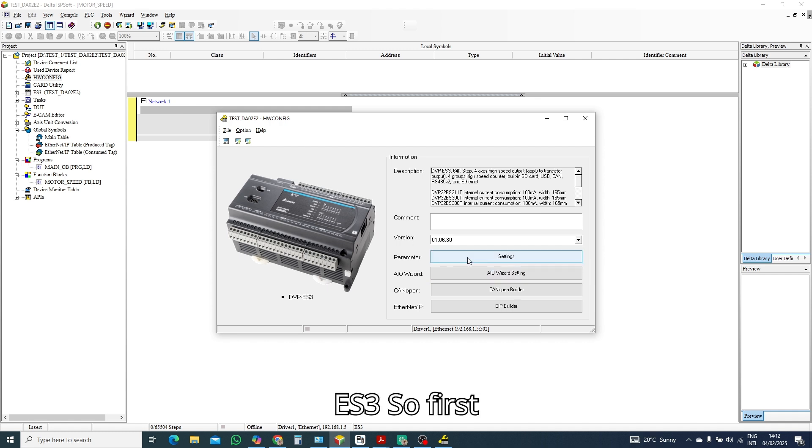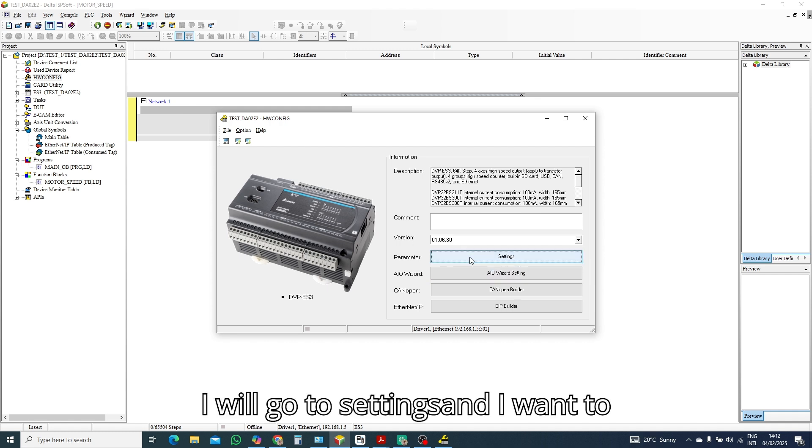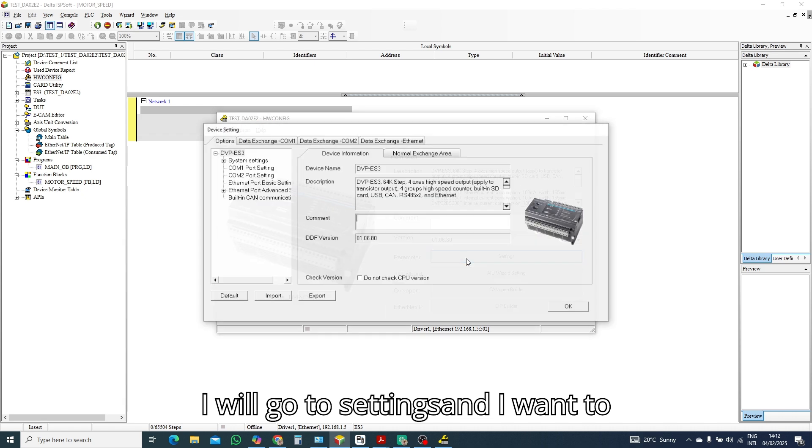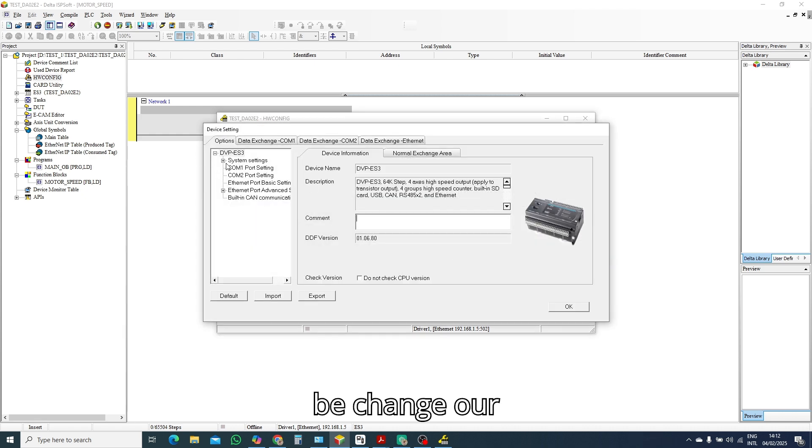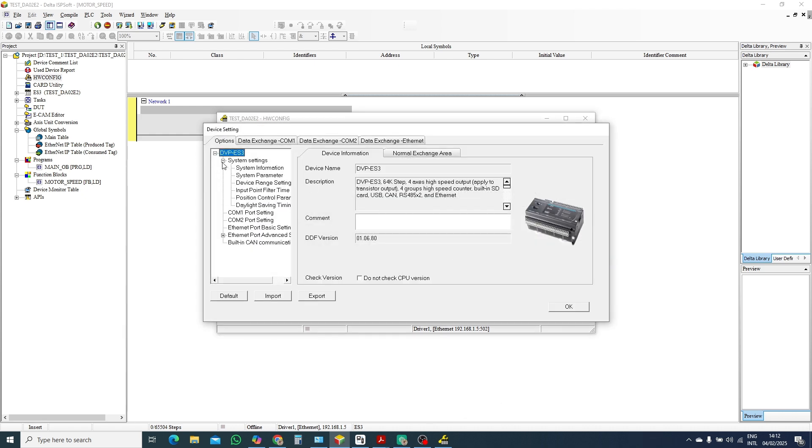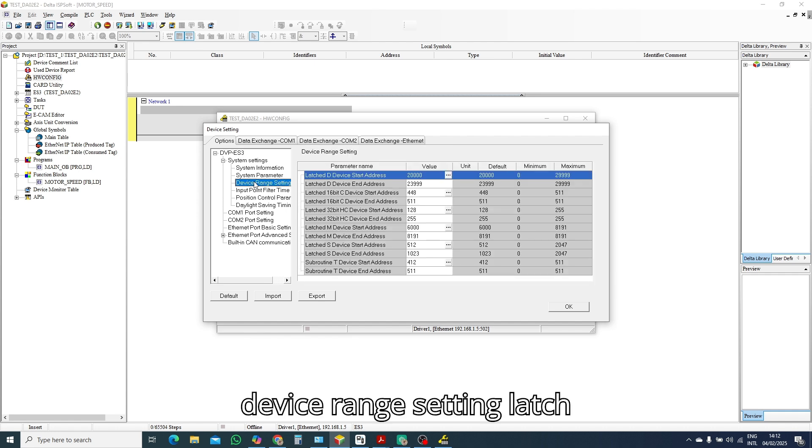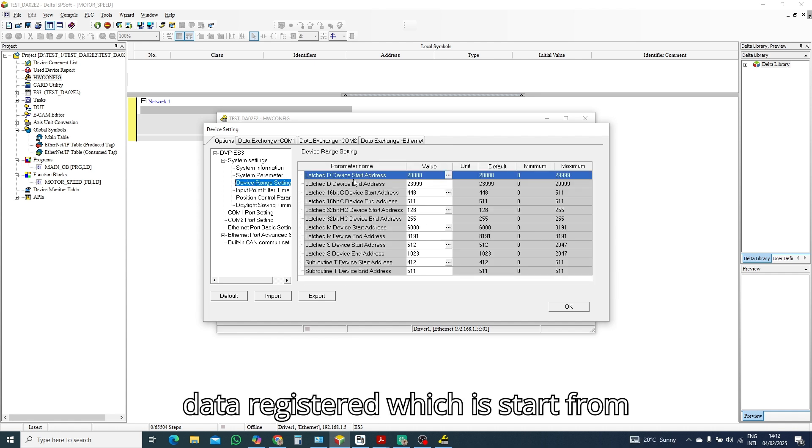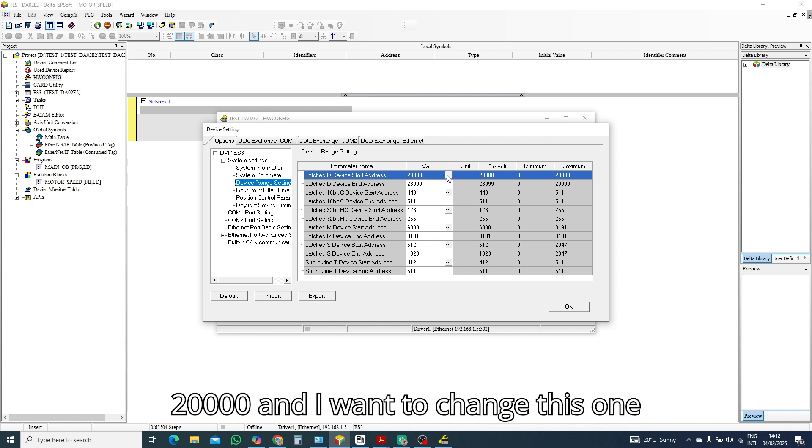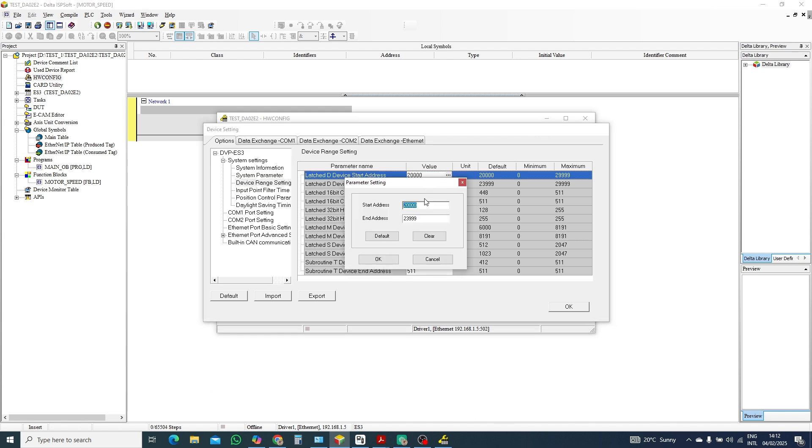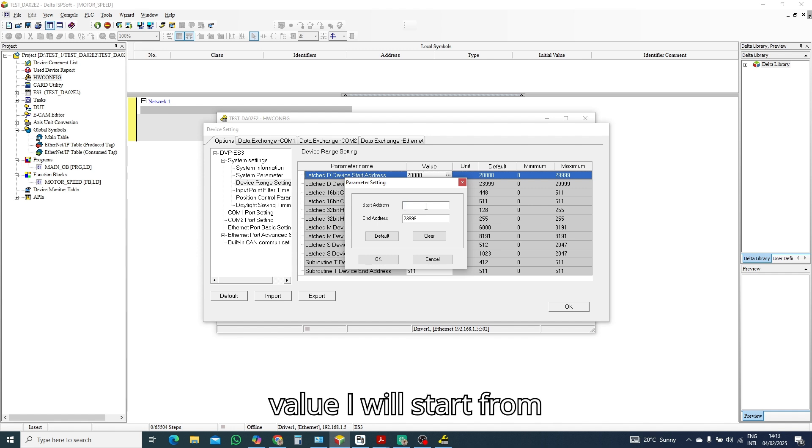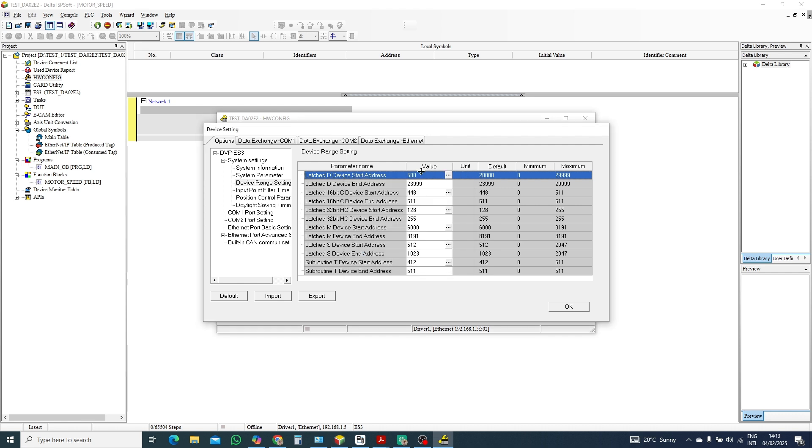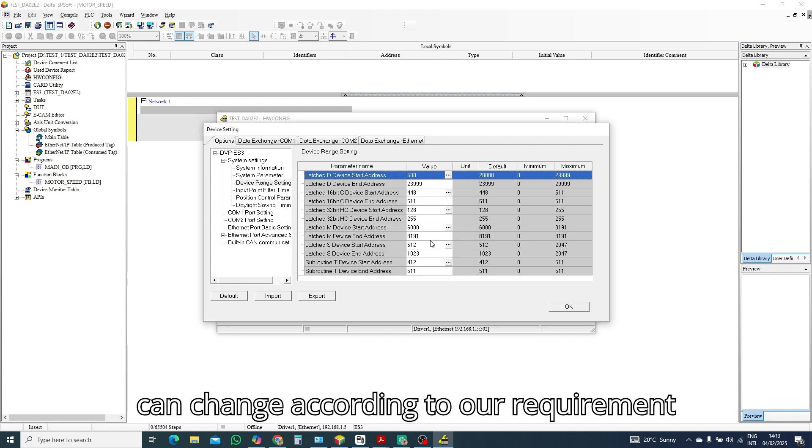So first I'll go to setting and I want to change our device range setting. Latch data register which will start from 20,000 and I want to change this one because my HMI is not accepting this value. I will start from 500. This we can change according to our requirement, latch values and data registers.